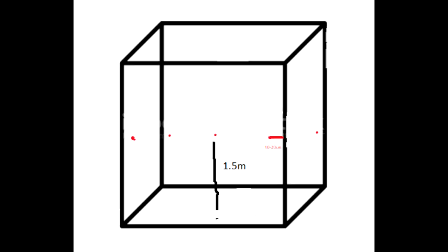When thoroughly measuring temperature in a room, you need to do it within 5 points, in the center and in 4 corners, at a distance of 10 to 20 centimeters from the walls, and 1.5 meters above the floor level. There are also specific 24-hour temperature variations.